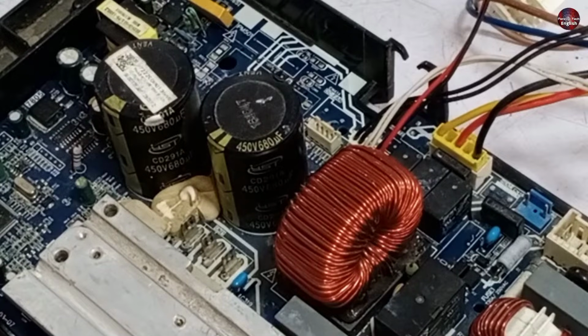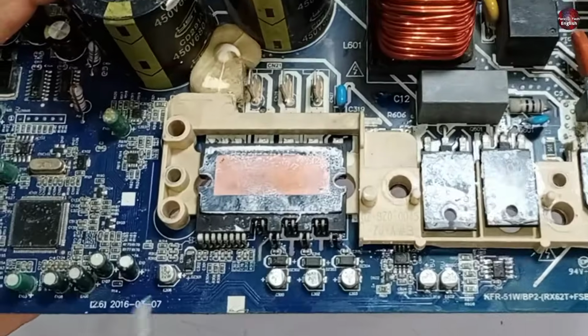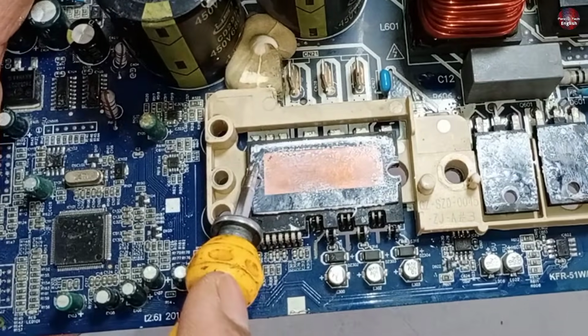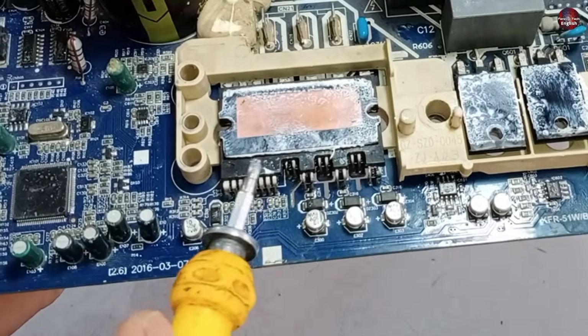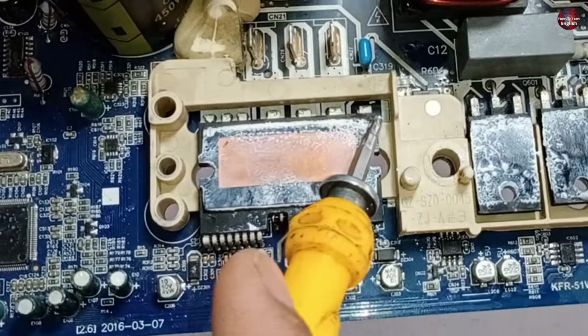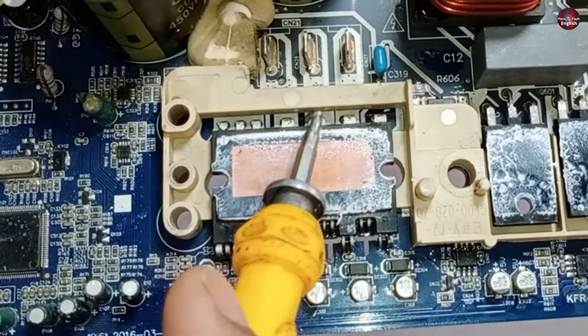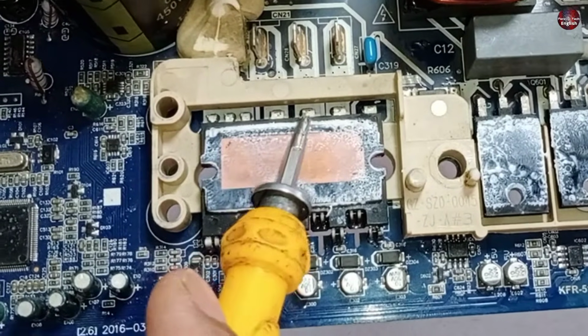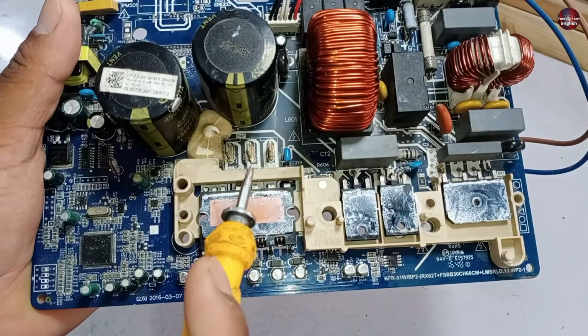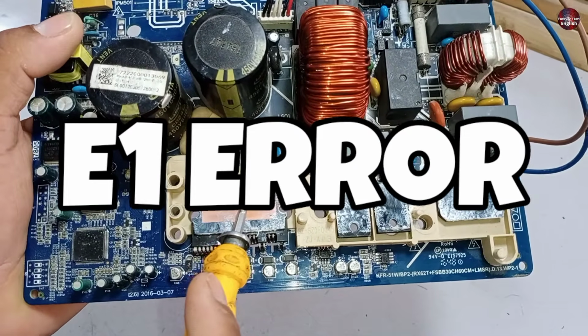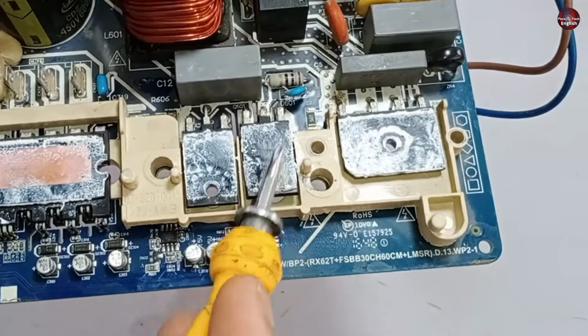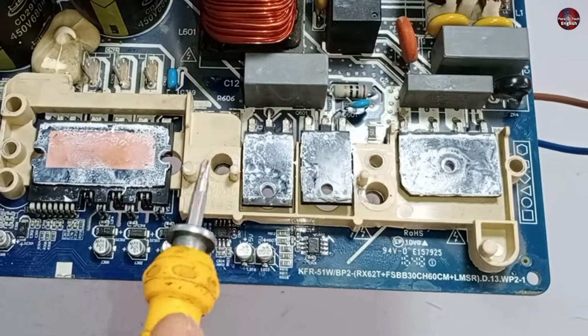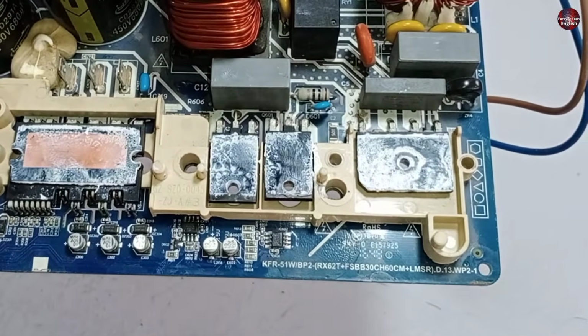Now let's talk about the further faults in the motherboard. If the high side of the IPM is faulty, because any one IGBT inside the IPM short circuits on the high side, then the motherboard will not power on. In this situation, it will show an E1 error. If its diode or IGBT short circuits, then still the motherboard does not operate.